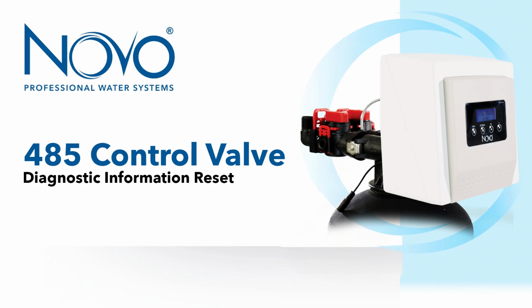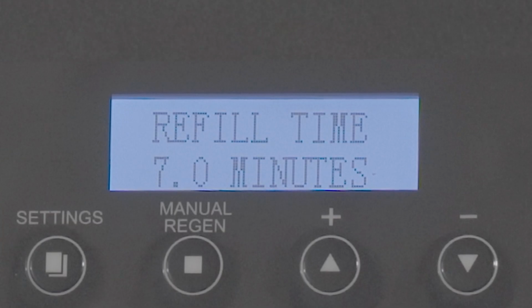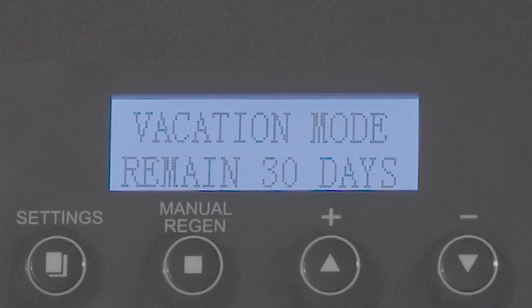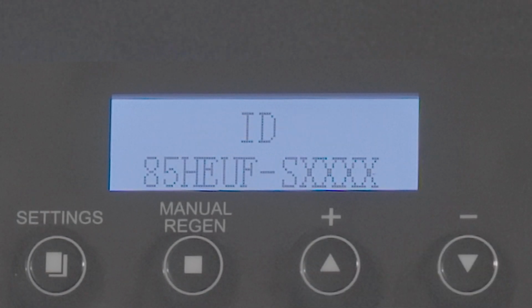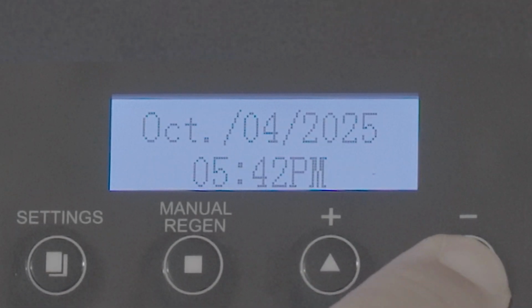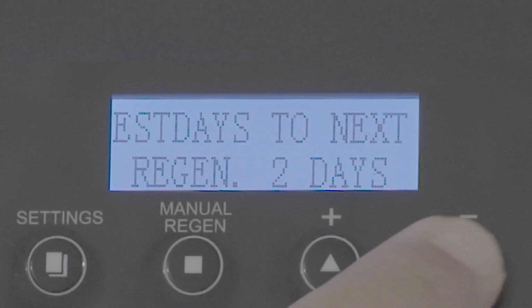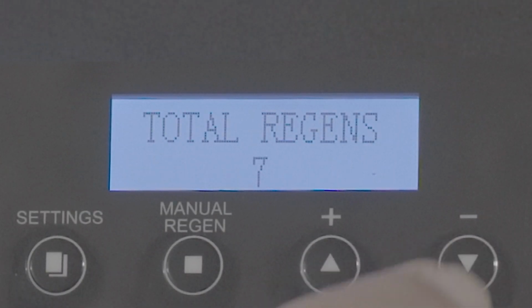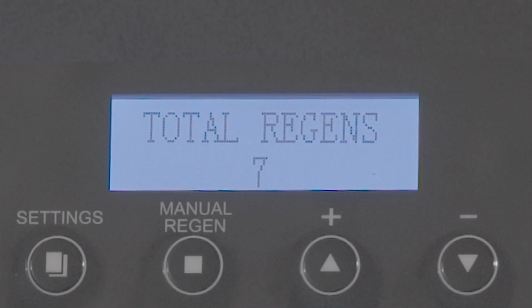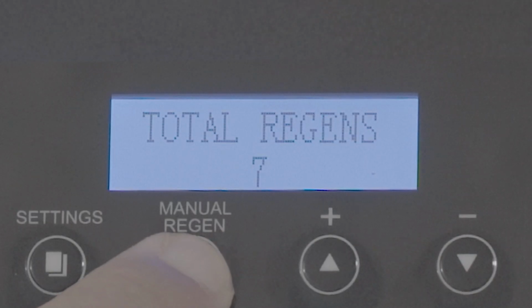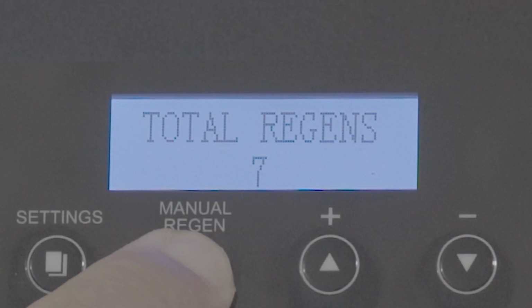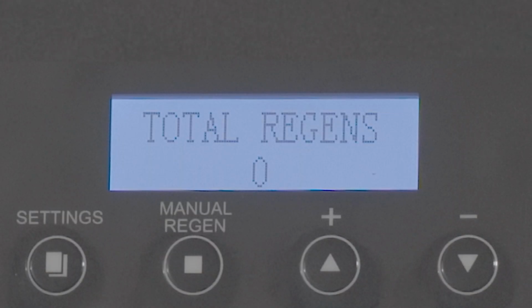In this video, we will show how to reset various diagnostic information. While the control valve is scrolling through its various diagnostic screens, you can freeze it by pressing the arrow down button. Continue pressing the arrow down button until you arrive at total regens. In this example, it shows that the unit has regenerated a total of 7 times since it was installed. If you would like to reset this value to 0, press and hold the manual regen button for several seconds until you hear a beep and the 7 changes to 0.